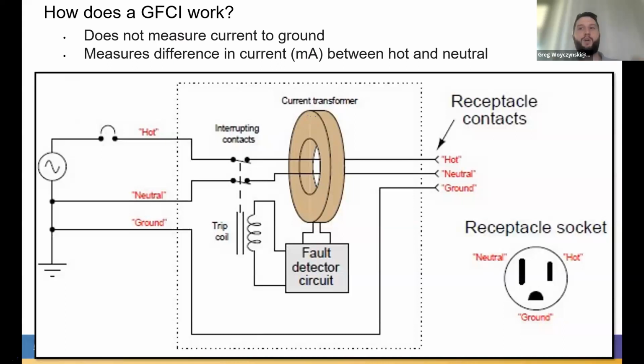What the GFCI is doing is measuring a differential current. It's taking a current clamp, just a donut, around your hot and neutral conductors and measuring the difference in current between your hot and neutral conductors. And the GFCI is assuming that that difference in current between the hot and neutral conductors is being passed to ground.